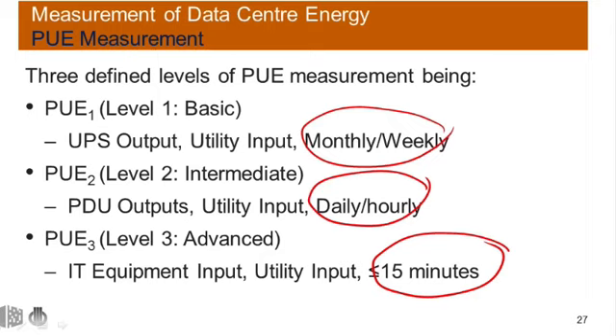So why is measurement of PUE so important? Well, if I compare a PUE of 1.6, which is fairly conservative, against a PUE of 1.15, which is absolutely achievable when best practice is followed, and there are a number of examples of that. If I consider a 2 megawatt data hall operating at around 85% utilization and a power cost of maybe 10 pence per kilowatt hour, that would equate to a power OPEX saving of around £650,000 per annum.